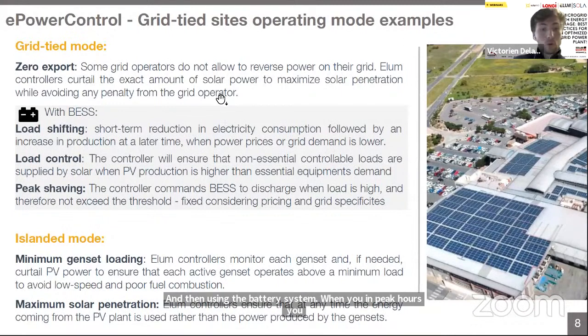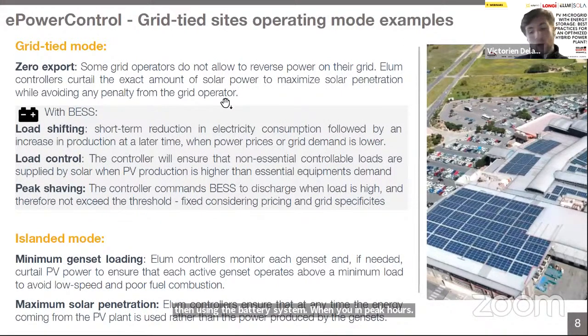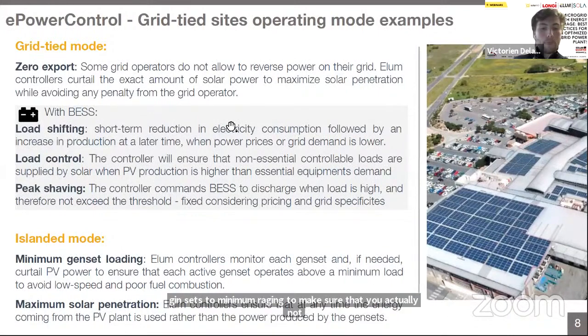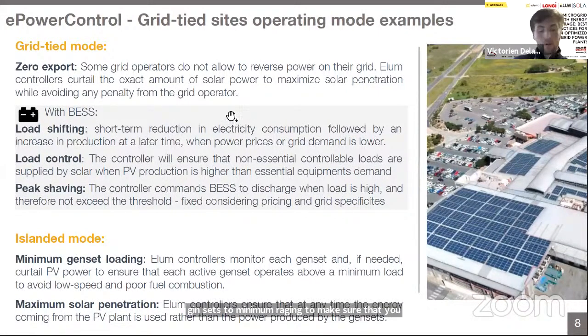You can also do load control. That's what Elum is doing on several sites. The controller is able, for example, to do breaker control -- opening breakers depending on conditions on site. And in islanded mode, of course, always ensuring minimum genset loading, to reduce fuel consumption while keeping gensets at minimum loading, making sure you're not using them in a bad way, and of course maximizing solar penetration.